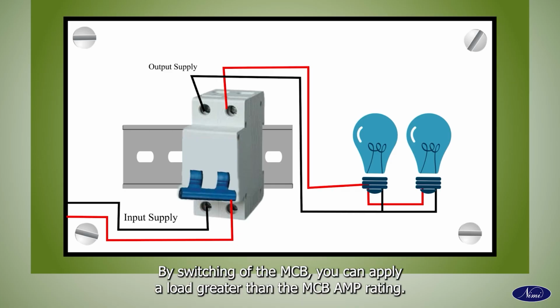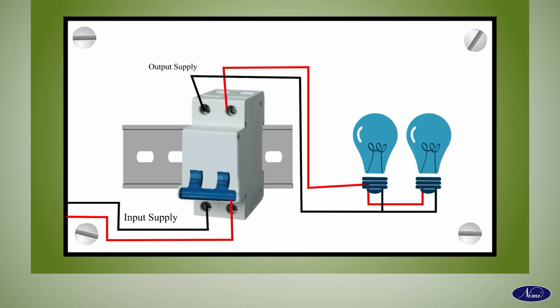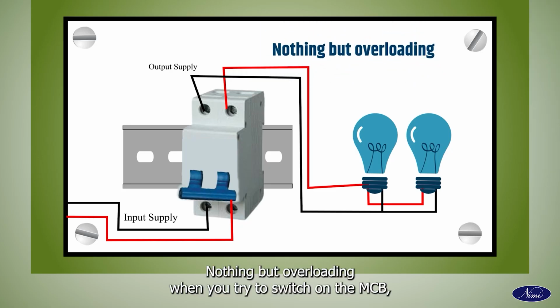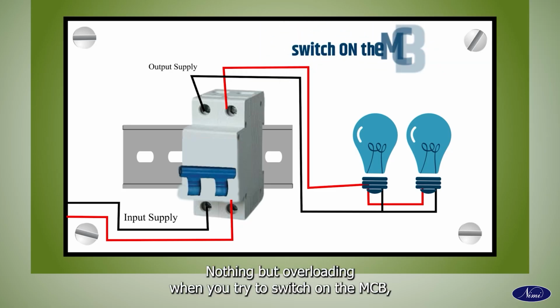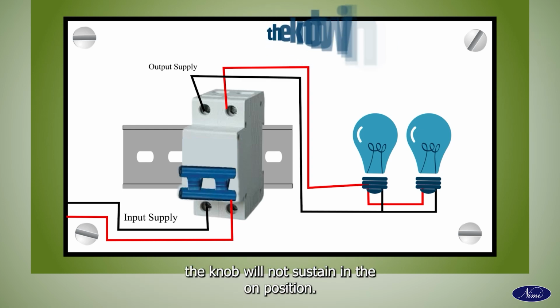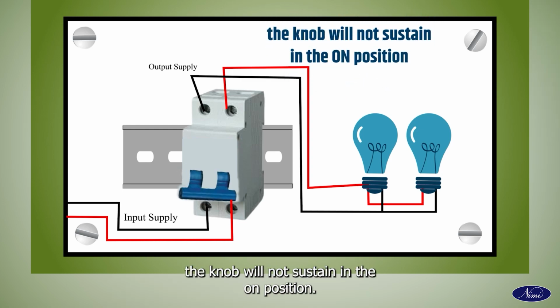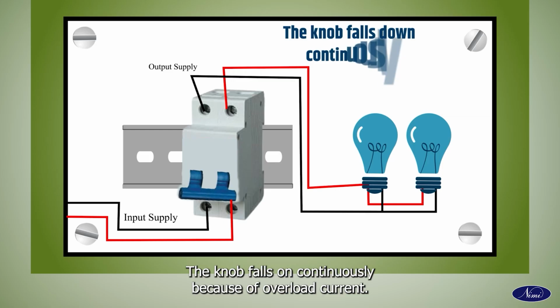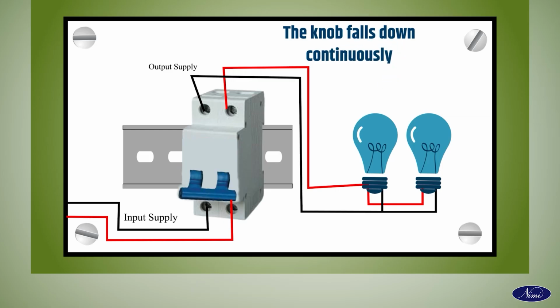By switching off the MCB, you can now apply a load greater than the MCB's ampere rating, which is nothing but overloading. When you try to switch on the MCB, the knob will not sustain in the on position. The knob falls down continuously because of overload current.